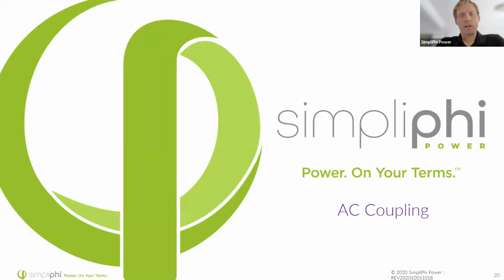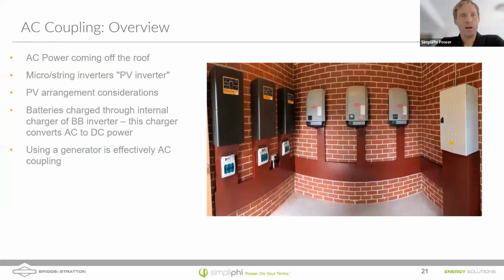So let's talk a little bit about AC coupling, and we'll get into some designs for that as well. With AC coupling, you've got AC power coming from your power source, and we say roof here, but that could be typically AC couples on roofs. You've got micro string inverters that are producing basically a PV inverter. PV arrangement considerations here: when coupling these panels, you need to make sure that we're not charging too fast. The charge controllers don't have as much control when you have microinverters producing AC power as they do with MPPTs. And so we need something to convert that AC power coming from the panels into DC to charge the battery bank.